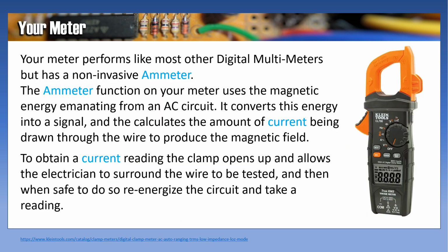The meter you are supplied with performs like most other digital multimeters, but has a non-invasive ammeter. The ammeter function on your meter uses the magnetic energy emanating from an AC circuit. It converts this energy into a signal and calculates the amount of current being drawn through the wire to produce that magnetic field. To obtain a current reading, the clamp opens up and allows the electrician to surround the wire to be tested, and then, when safe to do so, re-energize the circuit and take a reading.